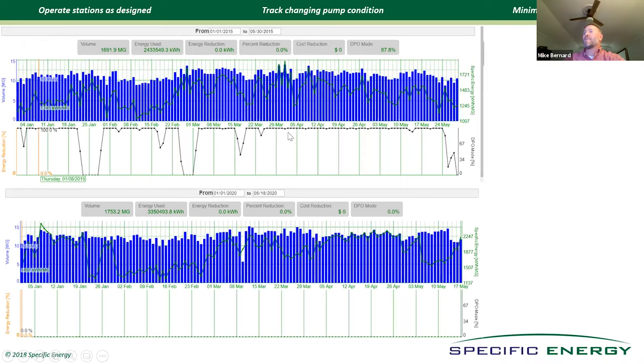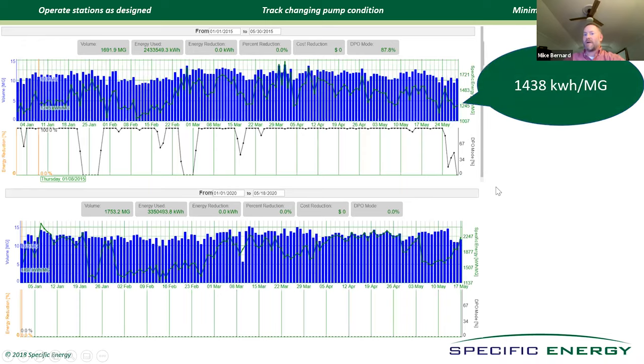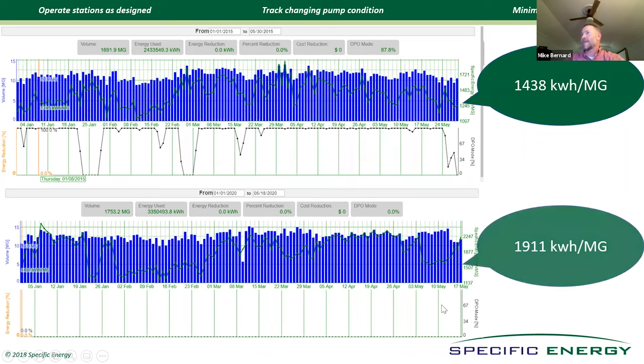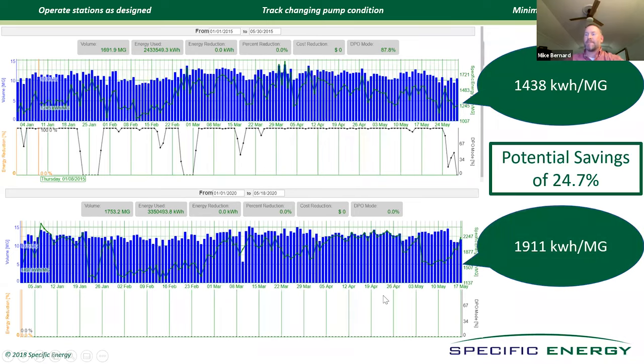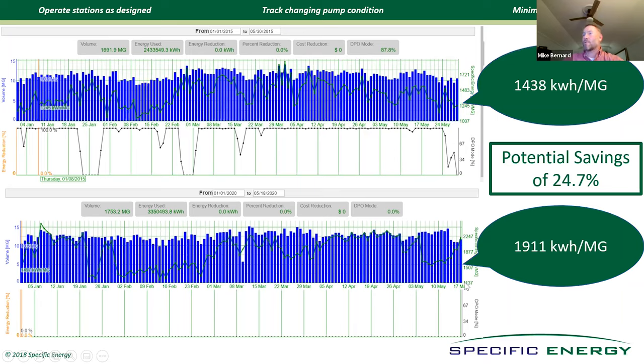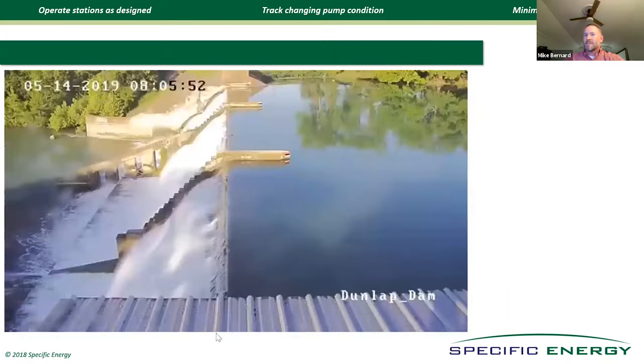And the energy savings, you see that these two dots aren't on top of each other. Well, that's just because we were operating off of a five-year-old model and these pumps had experienced more wear and tear. But I can tell you definitively that on this day, Casey operated at two different flow set points, basically low and high. At low flow set point, we were saving him about 36% energy. At high flow set point, it was more like about eight because he was moving closer to BEP. We can also go back in time and look in 2015. When they were in DPO mode for the first five months of the year, they were expending about 1400 kilowatt hours per million gallons. For the same first five months of 2020, they were spending about 1900 kilowatt hours per million gallons or a potential energy savings of 25%.